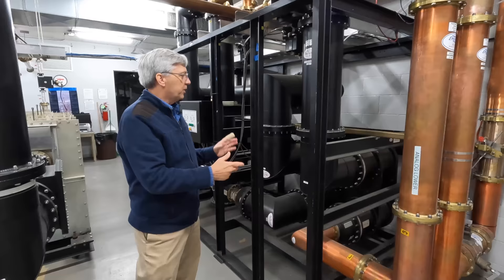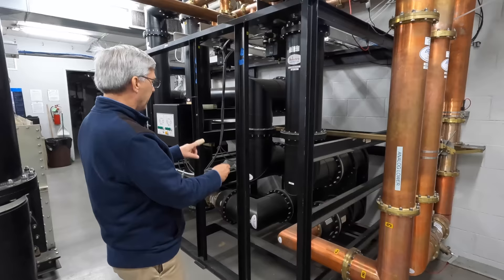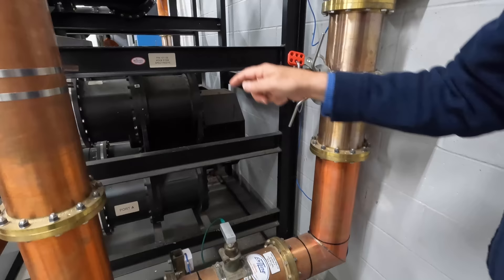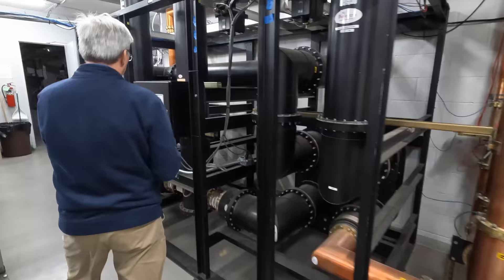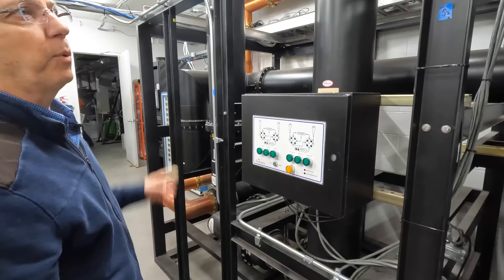This system is also an antenna switcher — it just has more RF to deal with. There's a four-port switch, just like we saw upstairs for the stations, only this is like a nine-inch version of the same thing. It's got a controller here so that we can switch the analog and digital antennas upper and lower, depending on what trouble we're having up there or even for regular maintenance at the top of the tower.